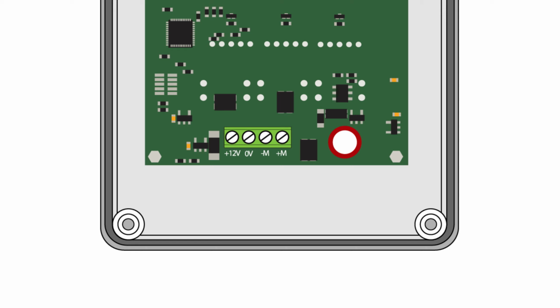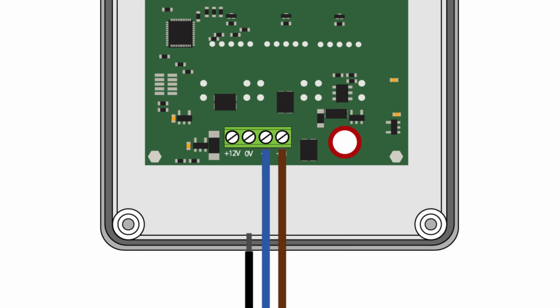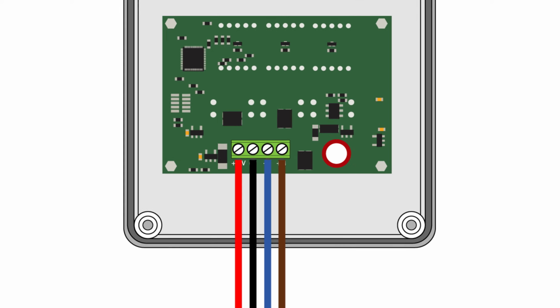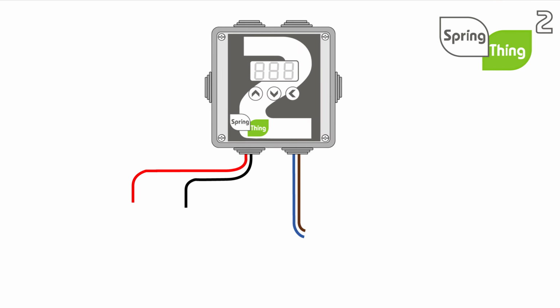To wire the controller, start by connecting the brown wire to the +M terminal. Insert the wire and tighten the screw terminal with a small screwdriver. Do the same for the blue wire to the -M. This will connect the pump. Connect the black wire to the 0V screw terminal. Then finally the red wire to the +12V screw terminal. Place the lid on the enclosure and tighten the screws.